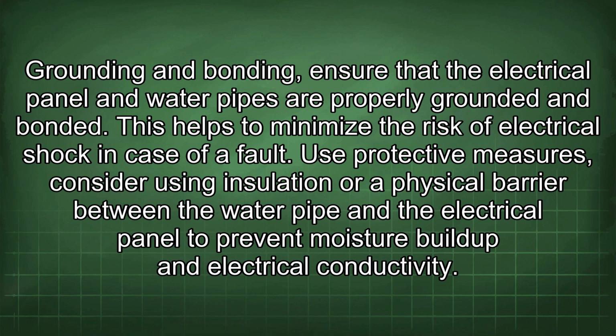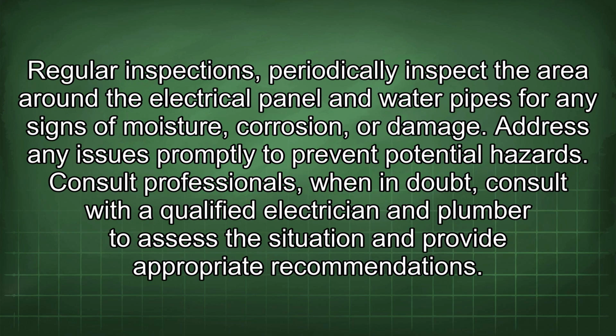Use protective measures. Consider using insulation or a physical barrier between the water pipe and the electrical panel to prevent moisture buildup and electrical conductivity. Regular inspections. Periodically inspect the area around the electrical panel and water pipes for any signs of moisture, corrosion, or damage. Address any issues promptly to prevent potential hazards. Consult professionals. When in doubt, consult with a qualified electrician and plumber to assess the situation and provide appropriate recommendations.